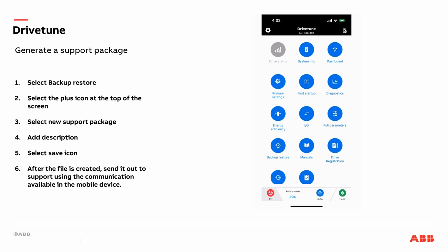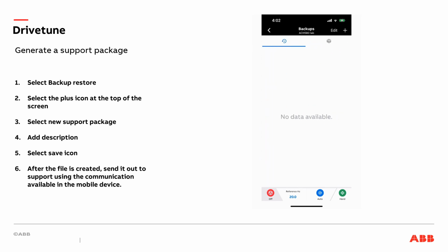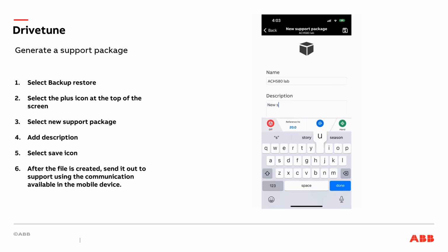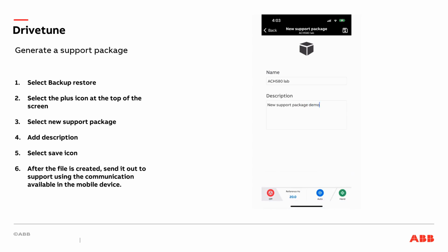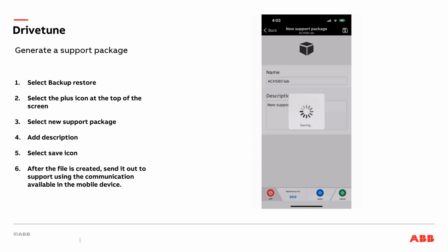I will now demonstrate the creation of a support package after connecting. After selecting the Backup and Restore button, then on the next screen selecting the plus button in the upper right-hand corner, and then selecting New Support Package, I take the step of adding some detail to the description of the file for reference. I then hit the Save icon in the upper right-hand corner of the screen. This will generate the file. It will take approximately 1 to 2 minutes for a support package file to be created. This file is typically created when there are questions about commissioning or the operation of a drive, and there is a need to review the programming in the drive.